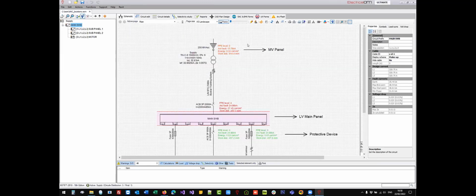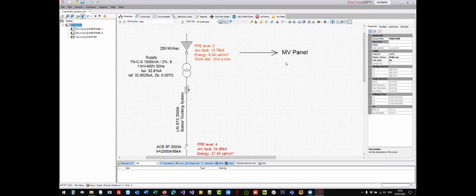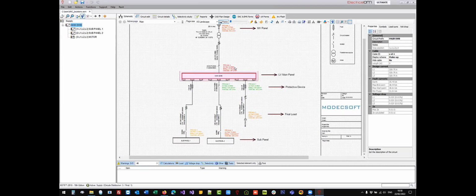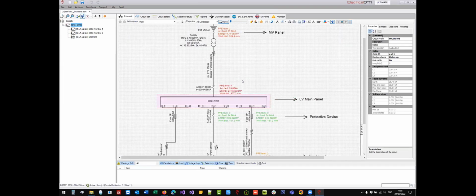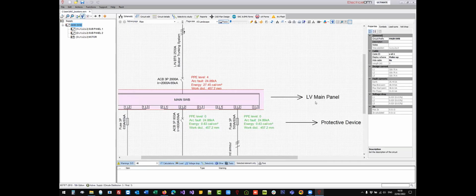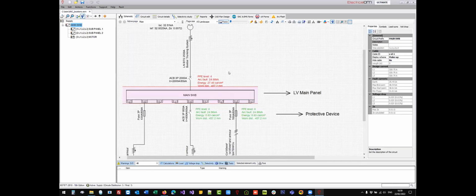First of all, in ElectricalOM, you can define the primary side of your low voltage transformer, the device used to protect the medium voltage panel, and we can perform arc flash assessment in this location. Then moving on, we can perform arc flash assessment on the low voltage side, and especially on the main low voltage panel, as we can see here.